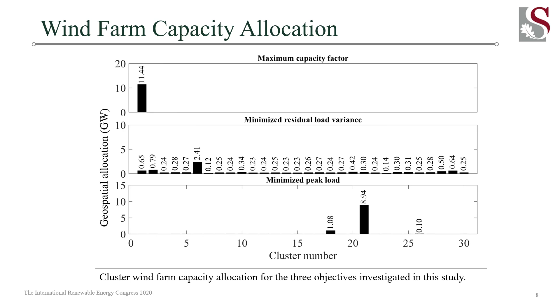So now we look at the impact of the allocations on the residual load profile. So here we see in the figure the average daily profiles for the national demand and the residual load of the optimized case studies. Now minimizing the evening peak load results in a large average reduction in the residual load during the peak period. This yields an average daily evening peak load that is of the order of 1 gigawatt lower when compared to the case study for minimizing the variance of the residual load profile.